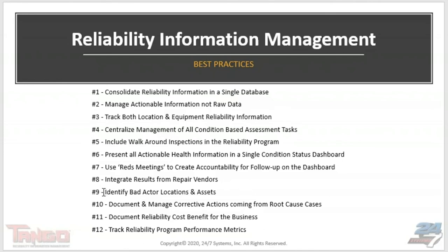Best practice number nine: routinely identify bad actor locations versus bad actor assets. Is it a problem with the location — a cooling tower where motors lack sealed bearings, or improper wash-downs needing education, or fluids stored incorrectly contaminating oil or grease? Or is it a motor carrying its problem from one base plate to another to another over its lifetime?